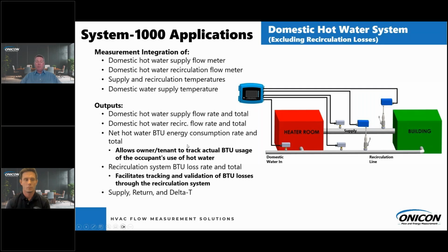So what does this do? It takes the total energy being generated by the heater room and then subtracts the energy being lost through your recirculation line. And so it allows the owner or the tenant to track actual BTU usage of the occupant's hot water usage. The recirculation specific BTU loss rate and total allows the facility owner or the facilities manager to track the losses in BTUs through the recirculation line so they can do improvements to the recirculation system, whether that's flow rate or insulation, so they can reduce those losses that the facility is paying through having a recirc line.